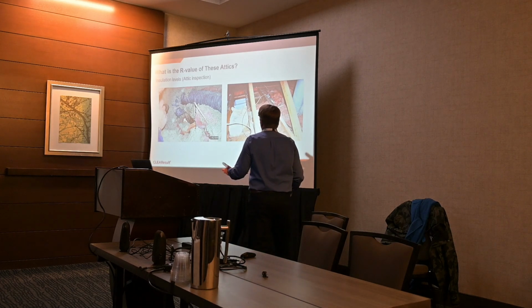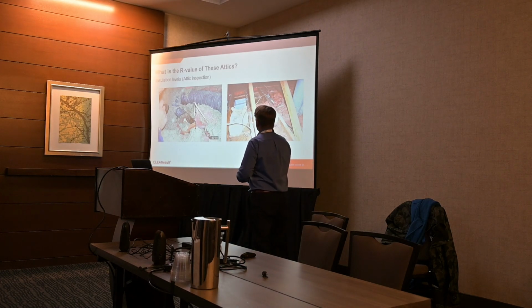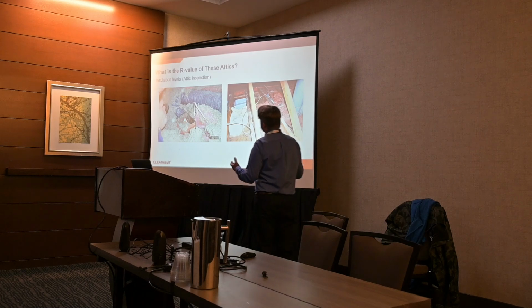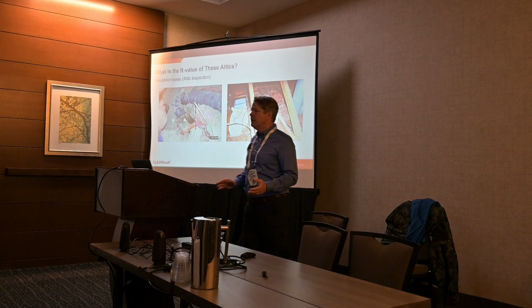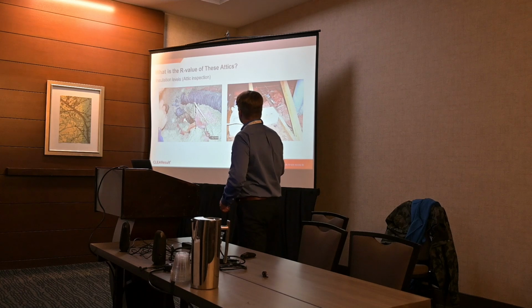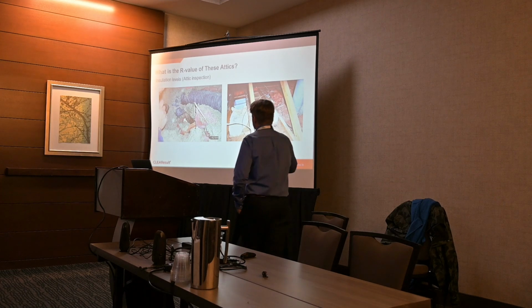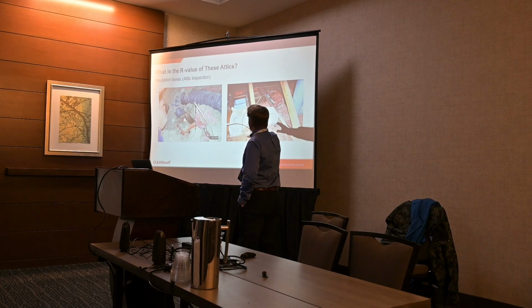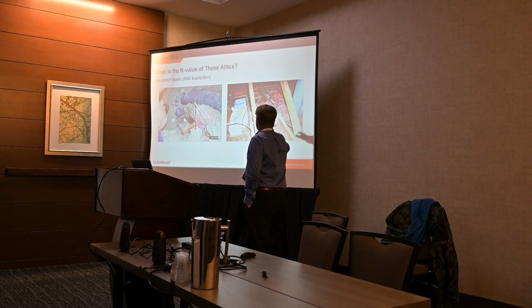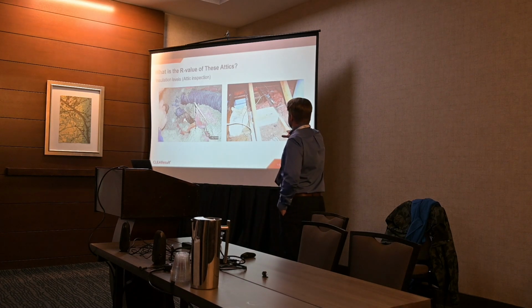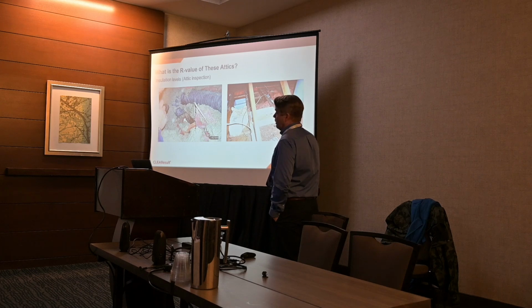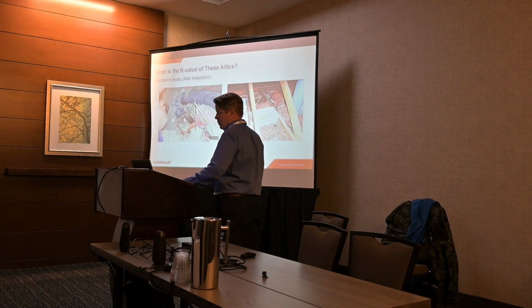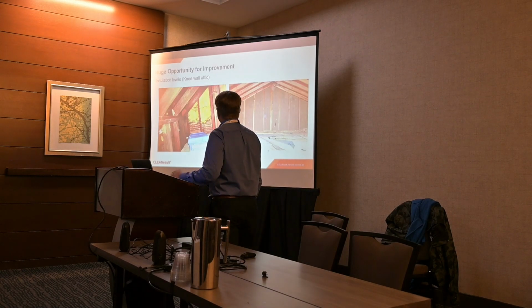Okay, so what's the R value of the attics that we run into? It's the rare attic these days, if people have access to an attic, they've been in there, haven't they, right? They put stuff all over the insulation, they've thrown the insulation around. Maybe they had some extra insulation, they threw it on there. So we need an accurate estimate of what that insulation level is, and then we're gonna bring it all the way up to at least code anyway, okay?